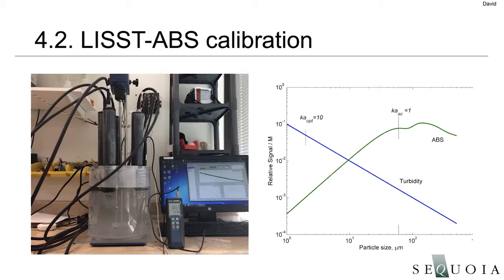So this is just a photo on the left side of our setup that we use for production testing in the lab. We have a tank that we've made specially for this that has baffles and a stirrer and arrangements for mounting the sensors in the right orientation and so on. And we have some special software that's used for collecting the output. Yeah, I just want to reiterate that what we're doing here is we're using the flat part of the curve of the ABS. So this is where we actually do the calibration.